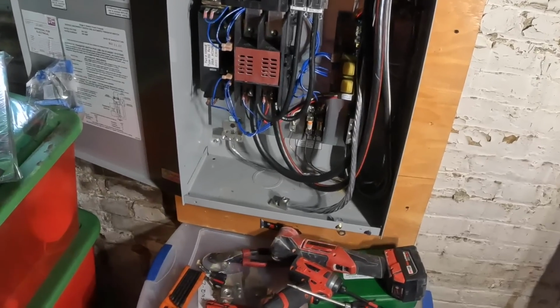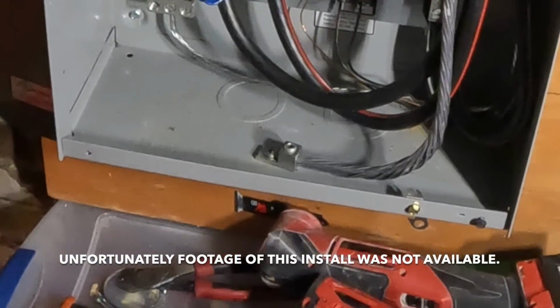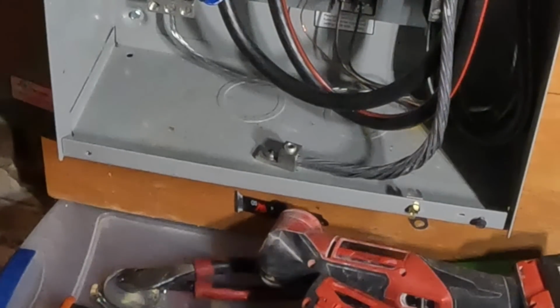I had to install a nut and bolt, a 1/4-20, and a lug to attach it to the enclosure because there wasn't a large enough terminal to attach this equipment grounding conductor to the enclosure. So I used a 1/4-20 nut and bolt.